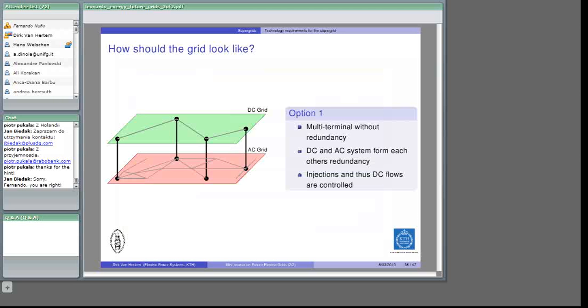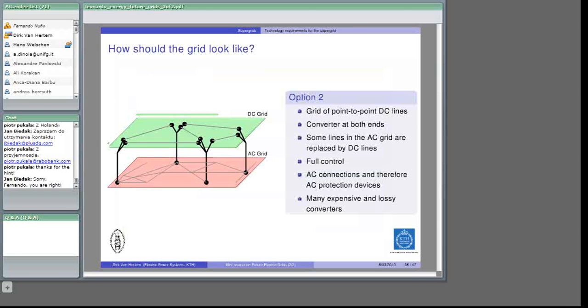A completely different setup might be that we don't have a real DC grid, but a grid of point-to-point DC lines. Every line in the DC grid is a separate line with a converter at both ends, so basically it's exchanging the AC lines with DC lines. This would allow full control, and another advantage would be that all the protection can be done at the AC side, which is much easier. However, you would need a lot of very expensive and very lossy converters, so maybe this is not the best way to go.